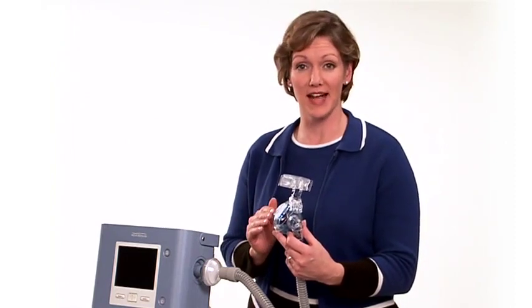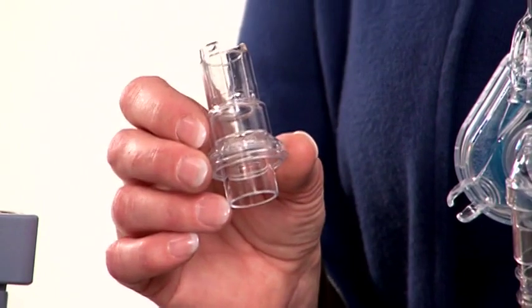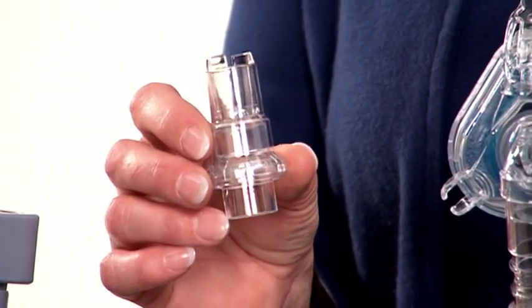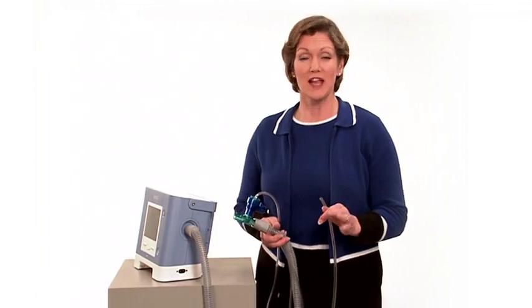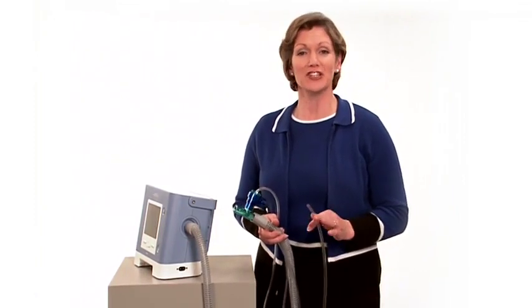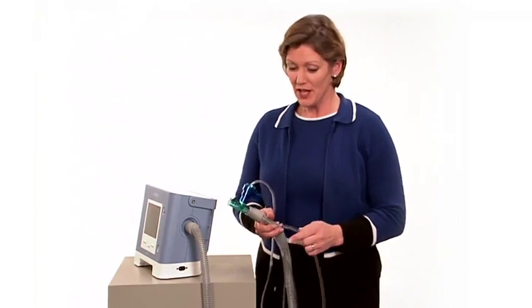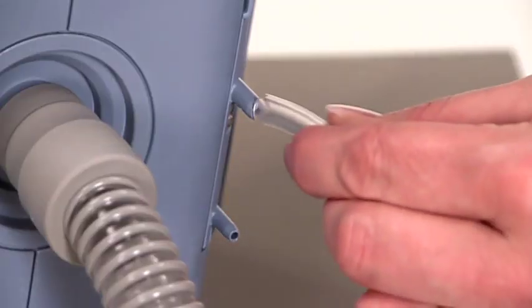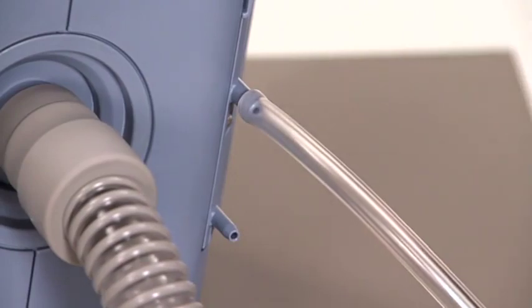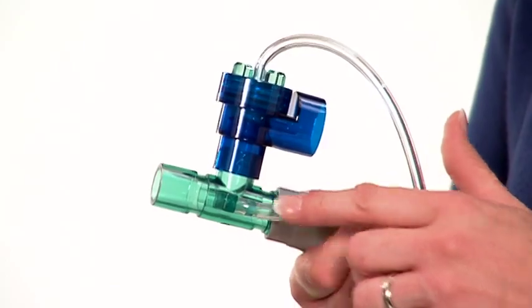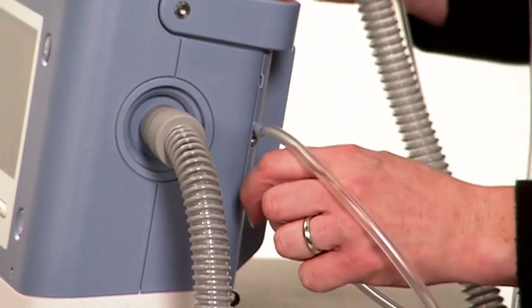Connect the other end of the tubing to a mask with a built-in exhalation port. If connecting to a trach tube or a mask that does not have a built-in exhalation port, connect a Whisper Swivel 2 exhalation port to the end of the tubing. If you're using a passive system, your breathing circuit is complete. If you're using an active system, there are 2 additional lines to connect, and you will have a different exhalation valve. The proximal pressure line attaches to the top connection on the active porting block. The other end of the tubing is attached to the proximal pressure port on the T connector. The exhalation valve control line fits onto the bottom port.